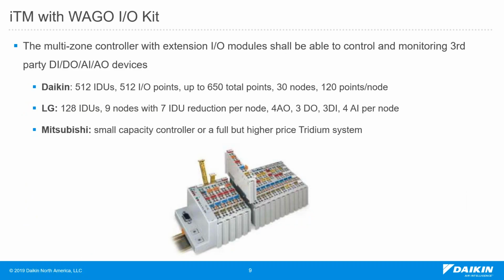So if we look into the ITM, when we integrate to the Wago IO kit, Daikin can integrate 512 indoor units and up to 650 total points can be integrated to the ITMs. It could be indoor units or it could be Wago IO points. And from the Wago IO structure, we can add like 30 Wago nodes, and each node can have 120 points or 120 sensors can be connected to each. So that's a big system.